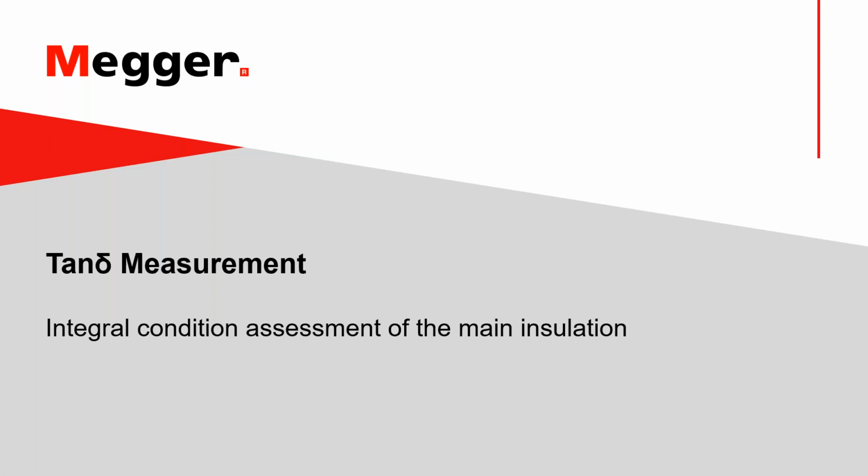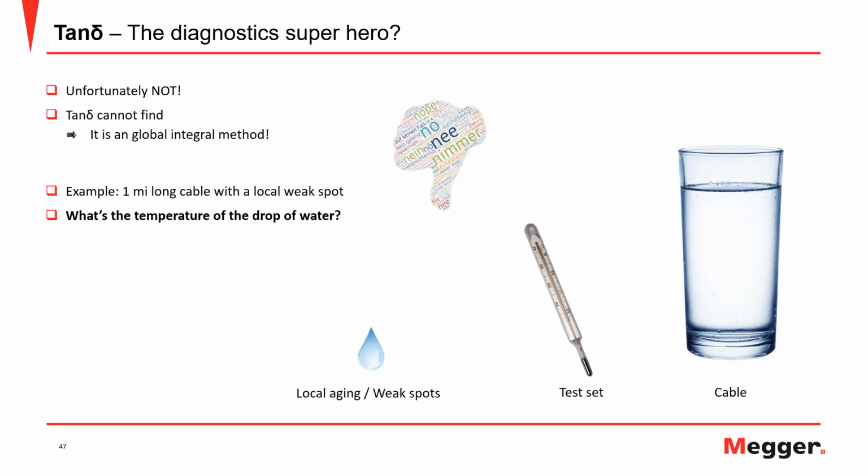Now the tan delta is the other one I told you. This circle there of the complete picture. And the tan delta was the test technology for the global issues like the integral testing. So is it the diagnostic superhero that some people think it is? Well, unfortunately not. It cannot find many faults or quite a significant amount of faults.